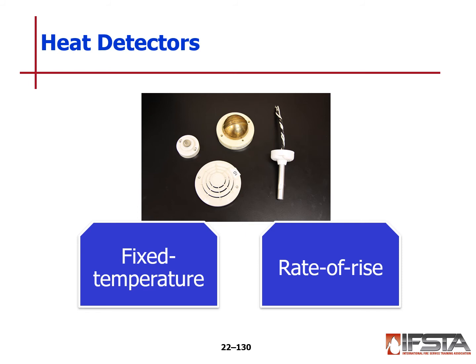Heat detectors may be fixed in this system. They can be fixed to a specific temperature, known as a fixed temperature. Say they're set at 500 degrees Fahrenheit. Then when it reaches that, it's going to alarm. And it could be rate of rise. So the detector is detecting what rate the heat changed and how drastically it changed.